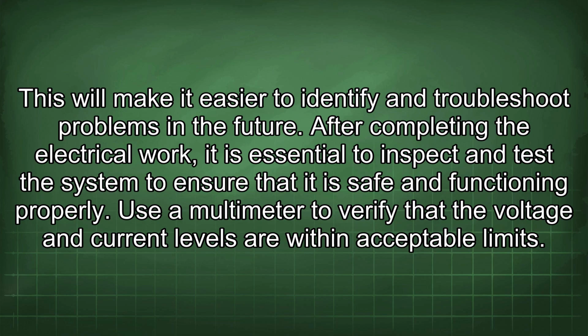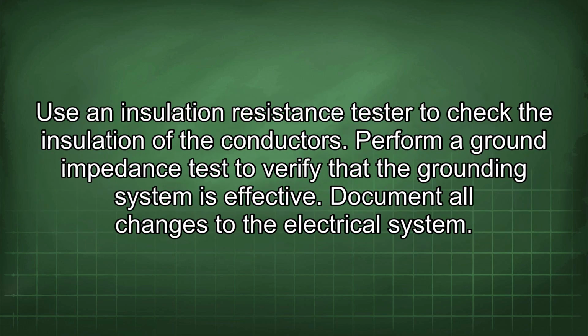After completing the electrical work, it is essential to inspect and test the system to ensure that it is safe and functioning properly. Use a multimeter to verify that the voltage and current levels are within acceptable limits. Use an insulation resistance tester to check the insulation of the conductors. Perform a ground impedance test to verify that the grounding system is effective.